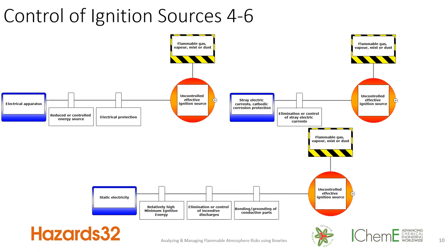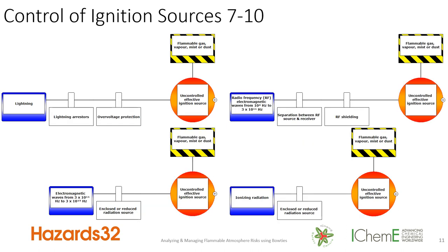Going through the subsequent sources — electrical apparatus, electrostatic influences — how are we going to prevent them from becoming credible, competent, effective ignition sources? They have to have the appropriate energy in order to ignite that flammable atmosphere. Continuing through lightning, electromagnetic waves, other radiation — all taken from clause six of EN 1127.